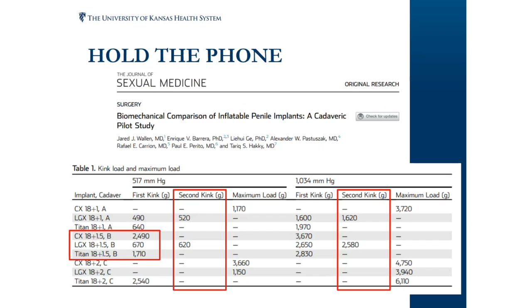The second kink just represents the fact that the device is not only bent once but twice, and it could significantly limit the usability in a sexual situation. And then if we look at full filling pressures, regardless of the actual device or how much rear tip, we see again at the full 20 psi, most devices have adequate penetration power.